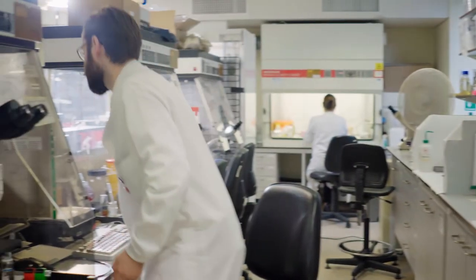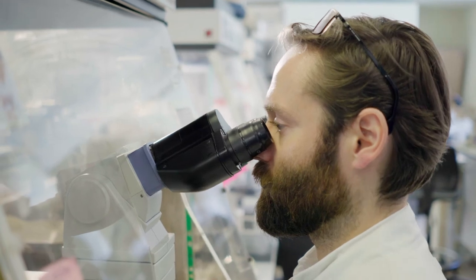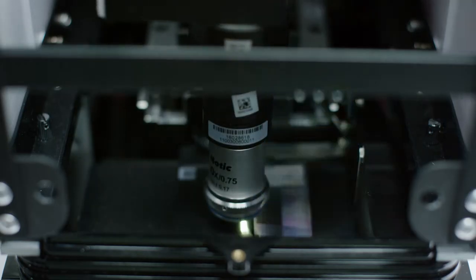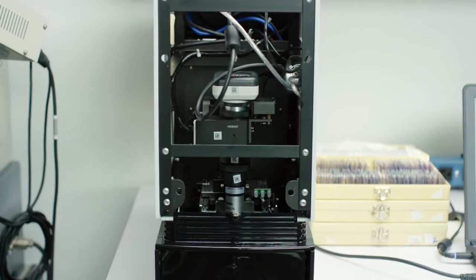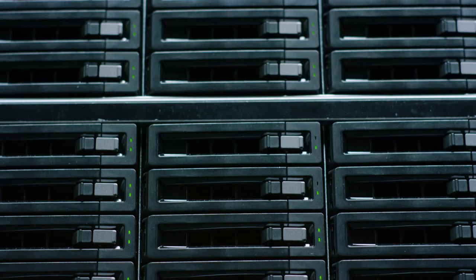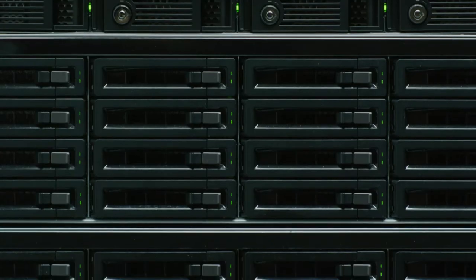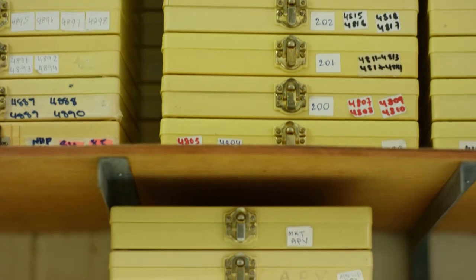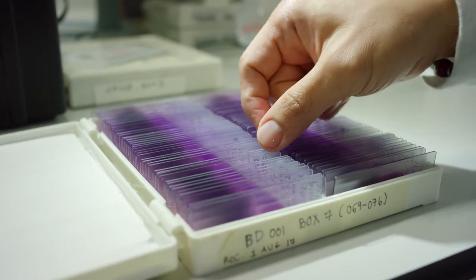The goal of the Easy Scan Go is to match the performance of a human microscopist when they're looking at a slide. To do that we use something called computer vision, where you train computers to see images the same way humans do. This is done with machine learning methods, specifically deep learning methods, which are one of the cornerstones of artificial intelligence. To develop the algorithm we collected a database of thousands of slides and used that data to train our algorithms to find the malaria parasites.